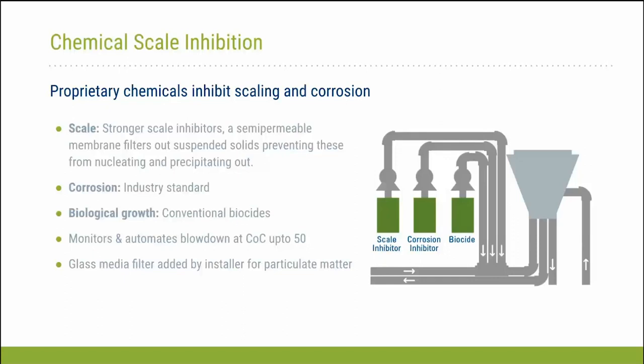So for this particular system, they're using the same corrosion inhibitor and the same biocide, and are using a much stronger scale inhibitor. And so in this particular case, it's still a chemical-based water treatment system with a stronger scale inhibitor. It does have a new manufacturer-specific control and automation system. They claim to be able to operate up to a COC of 50. We did not see that in this demonstration, but you will see that there was still very significant water savings.